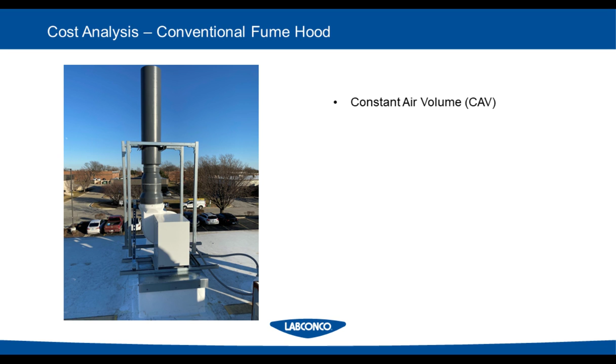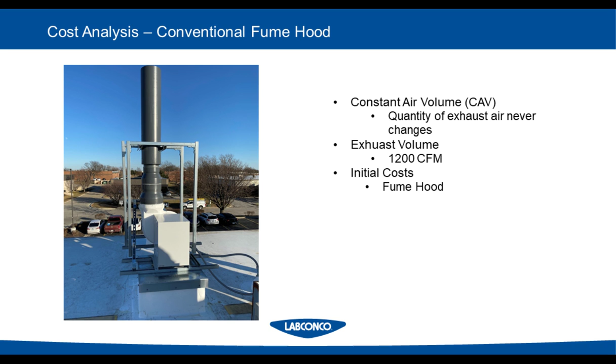For this analysis, we're going to use a specific exhaust volume of about 1,200 CFM. This is pretty typical for a conventional 6-foot benchtop fume hood. The initial costs on this would include the fume hood itself, as well as the building infrastructure - the mechanical, electrical, and plumbing. We're going to take a look at this in a table format.